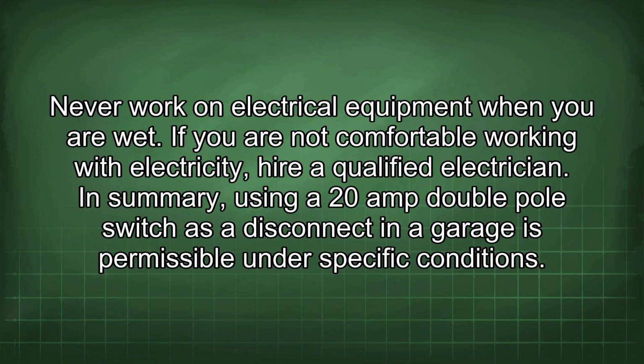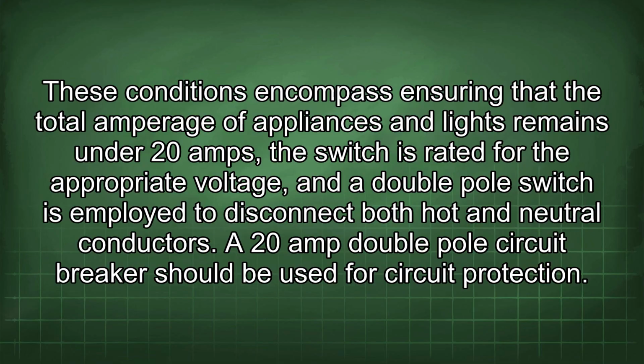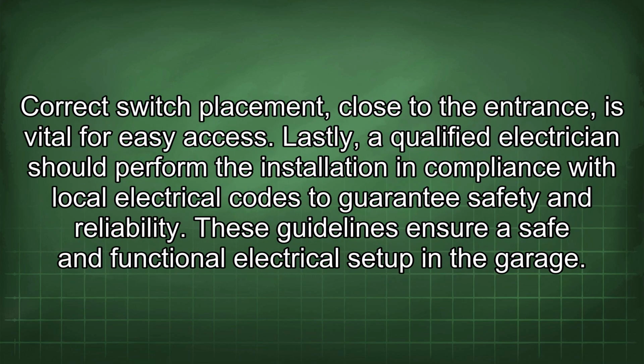In summary, using a 20 amp double pole switch as a disconnect in the garage is permissible under specific conditions. These conditions encompass ensuring that the total amperage of appliances and lights remains under 20 amps, the switch is rated for the appropriate voltage, and a double pole switch is employed to disconnect both hot and neutral conductors. A 20 amp double pole circuit breaker should be used for circuit protection. Correct switch placement close to the entrance is vital for easy access. Lastly, a qualified electrician should perform the installation in compliance with local electrical codes to guarantee safety and reliability. These guidelines ensure a safe and functional electrical setup in the garage.